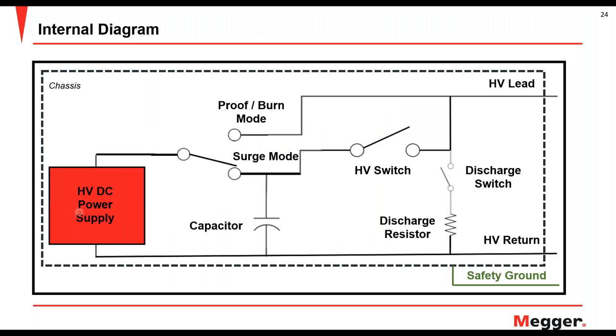The internal diagram of a thumper — any thumper — follows the same basic principle. You have a high voltage power supply, then a switch that can go to surge mode (thumping) or burn mode (high pot). Your high voltage switch and capacitor work hand in hand. In surge mode, you build the capacitor up to full voltage, close the high voltage switch, which outputs to your high voltage lead. You also have your return connected to the concentric neutral, so whenever you output voltage it comes back on the high voltage return — that's how you know your fault distance on arc reflection. The discharge resistor will bleed any high voltage off.